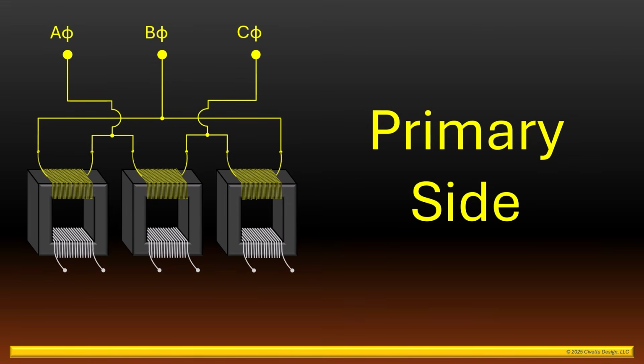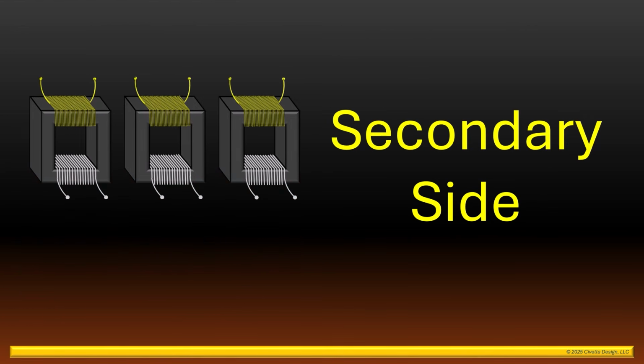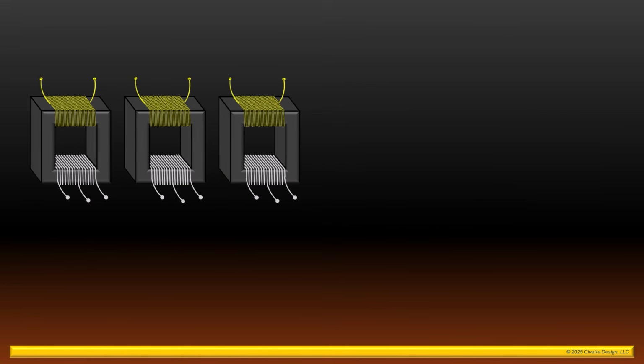Now that we know how the primary side of this transformer bank is connected to the primary system, let's move that aside and take a look at how the secondary side is connected. The secondary side of this transformer bank is going to be connected exactly the same way. We'll start with the secondary winding of the middle transformer. We'll also call this number 2, and then the winding of transformer number 1.